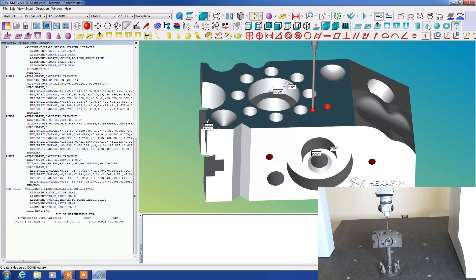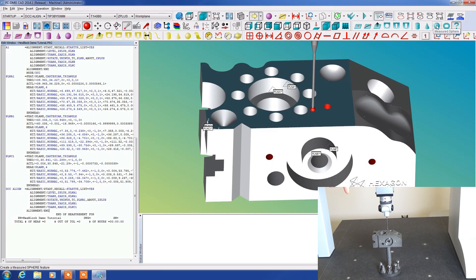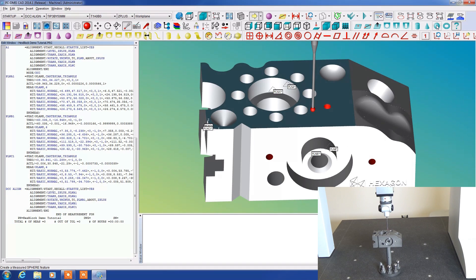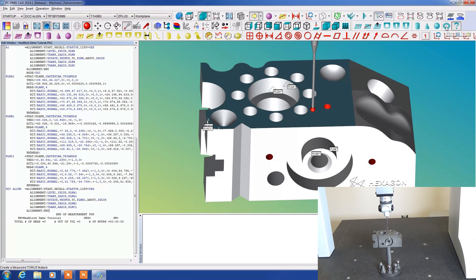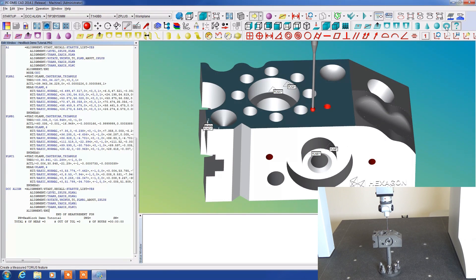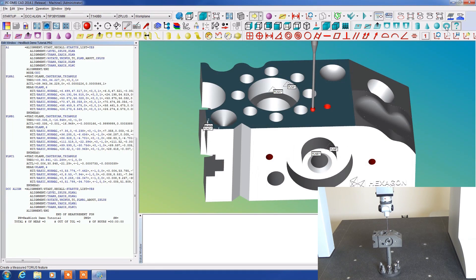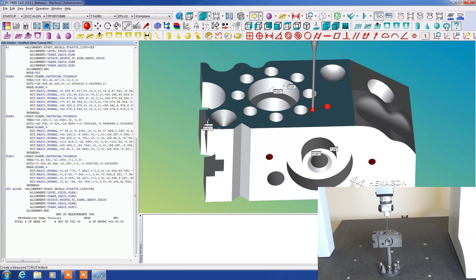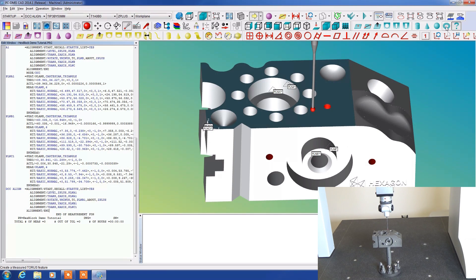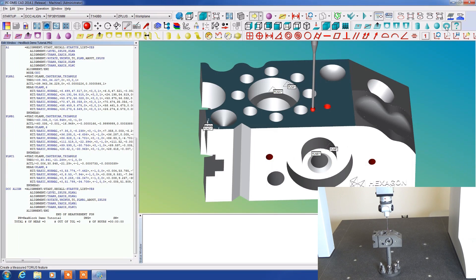A sphere typically you want to take a measurement on the top of the sphere and then you want to take several levels around it much like we did when we were working with the calibration sphere. I don't have any experience measuring a torus at this point. I would say be very diligent to make many measurements around the torus. I would not try that in guess mode. I don't think it will come back with the right result. But since it's a donut shaped piece you probably want to make some measurements inside the circle, outside the circle, and then several around on the raised edge of it in order to fully encapsulate that shape.